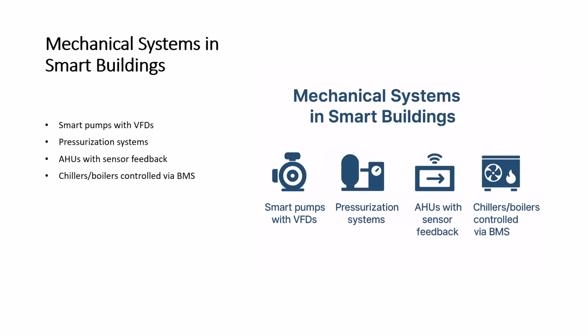VFD stands for variable frequency drive. Our smart pumps work on the principle of controlling the pump's motor speed by adjusting the frequency and voltage of the electricity it receives, so the power we provide reflects exactly in the motor speed. This affects the pump's velocity and pressure. So precisely, our pump curve is directly related to the frequency and voltage of electricity we provide, which decides our pump curve parameters.